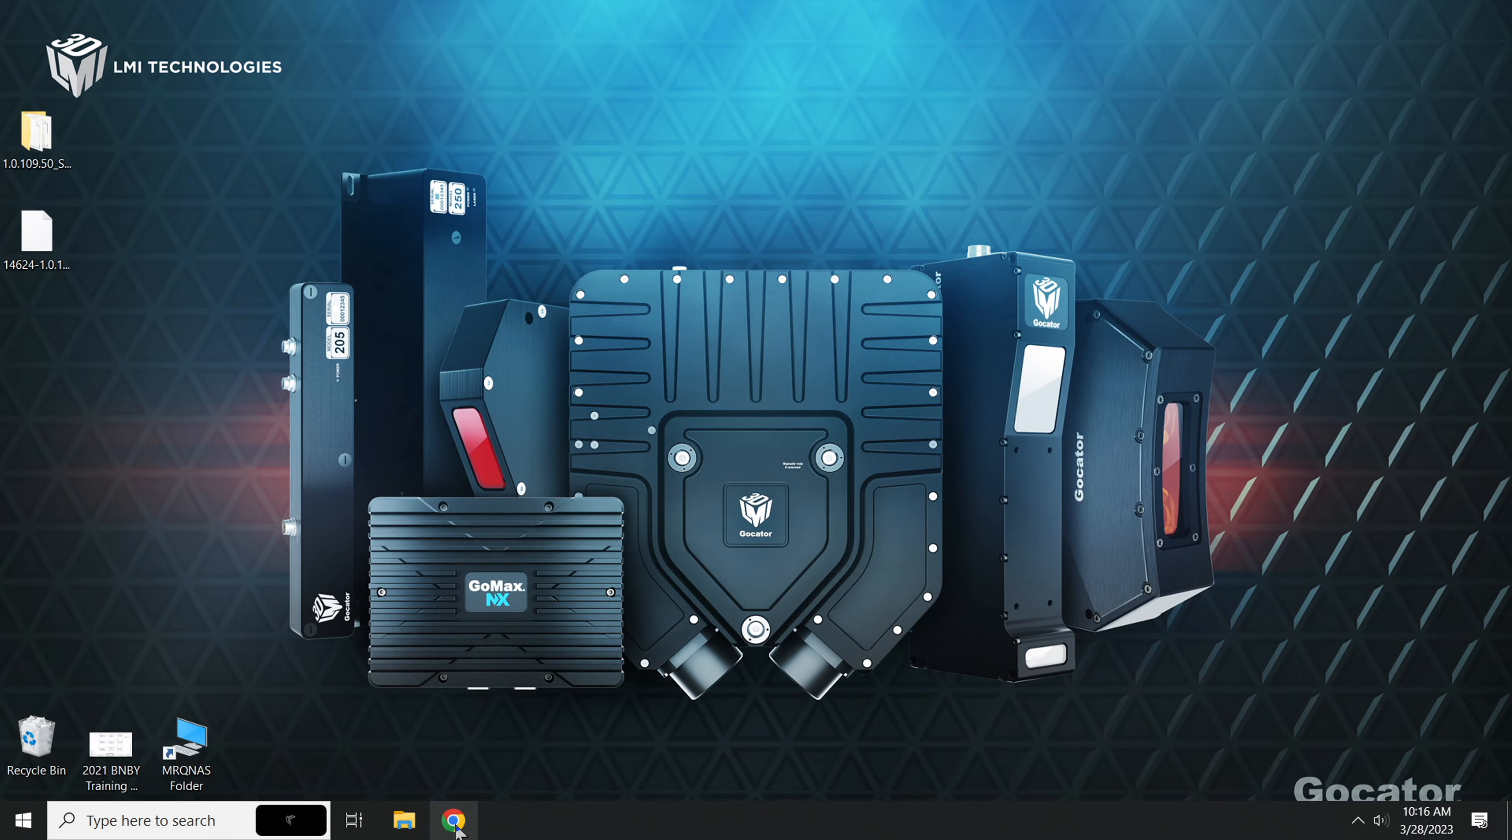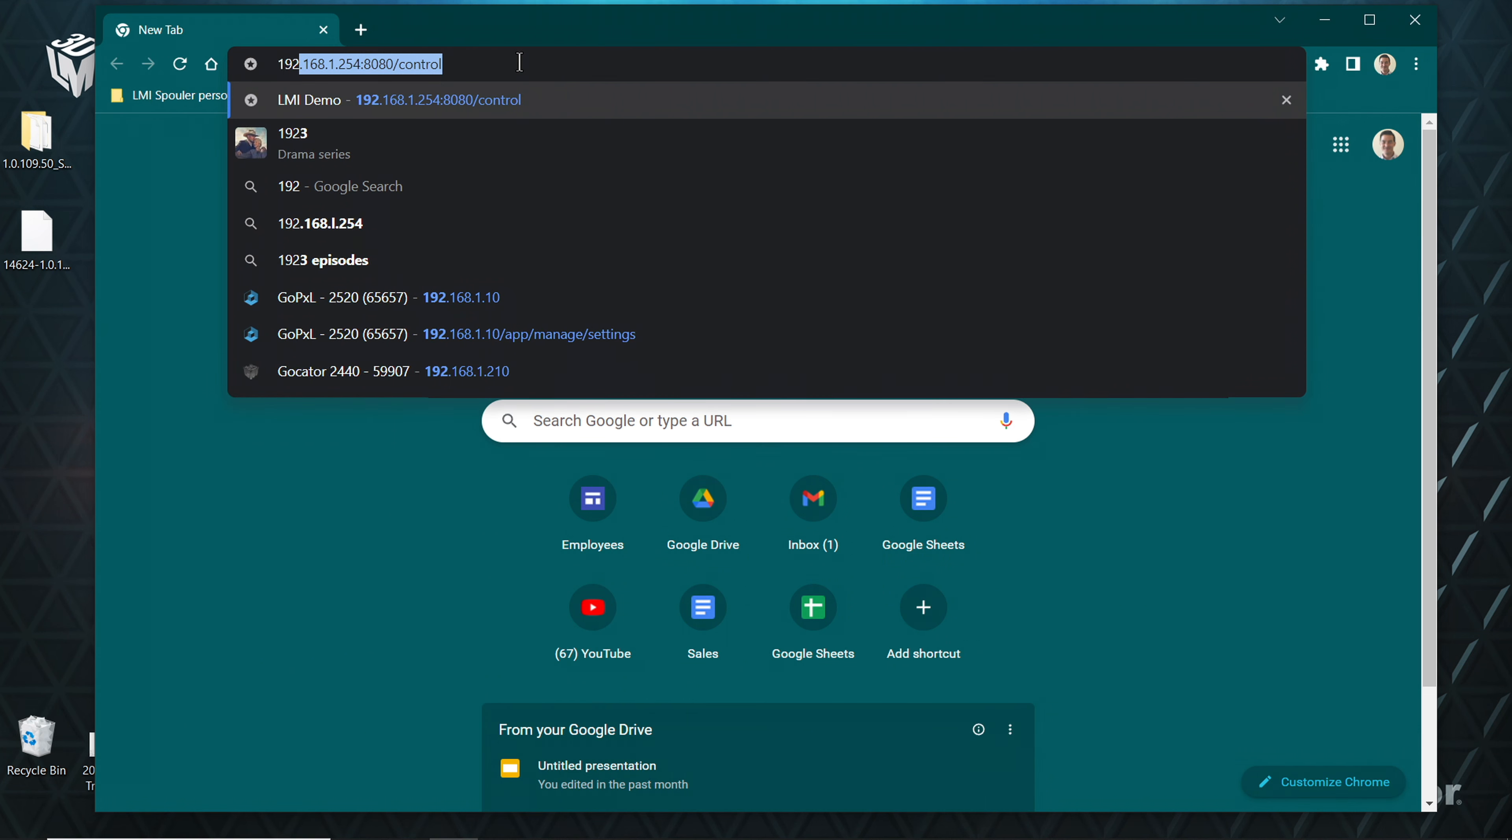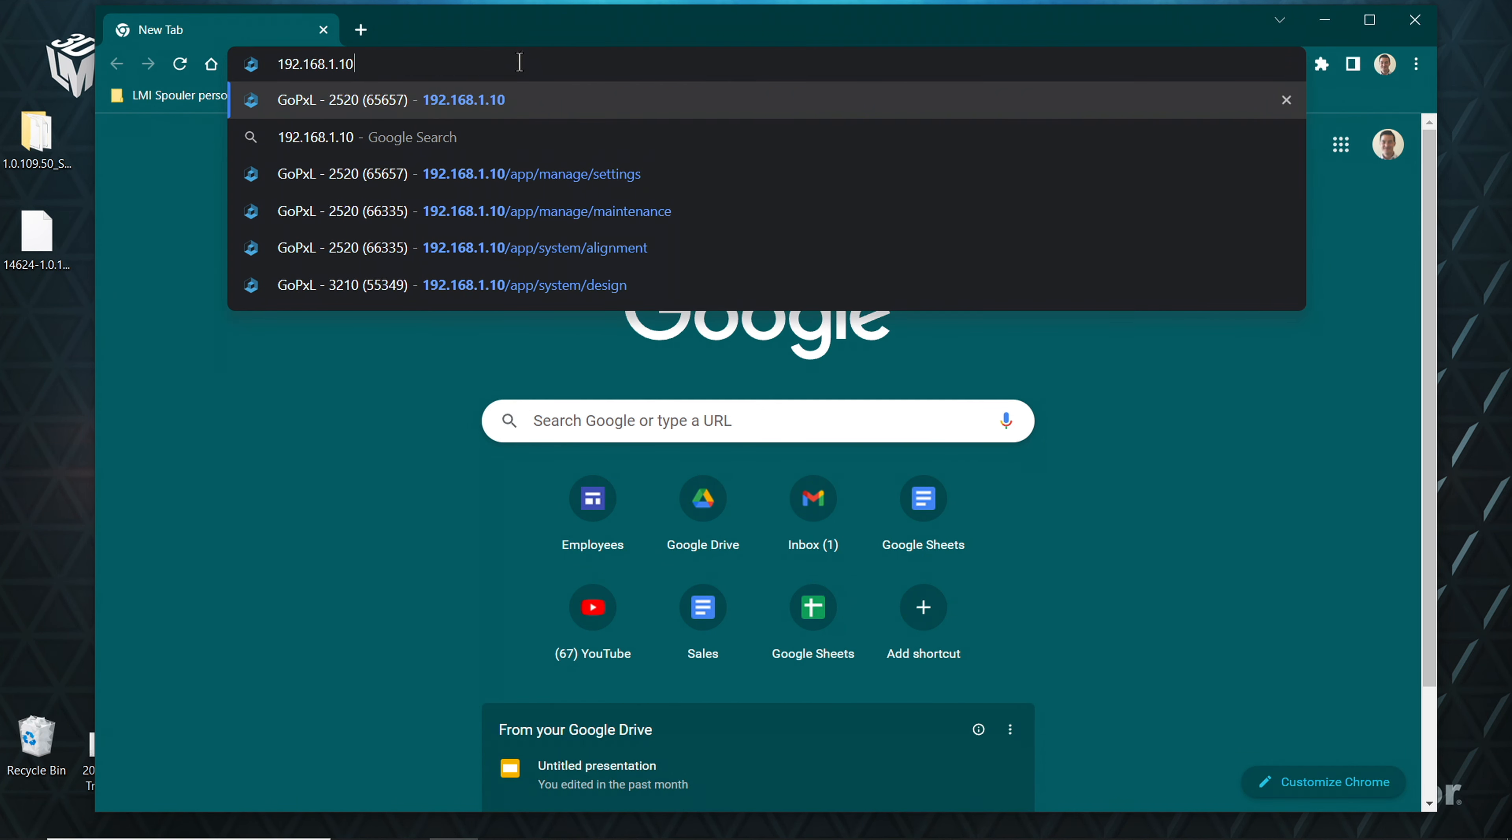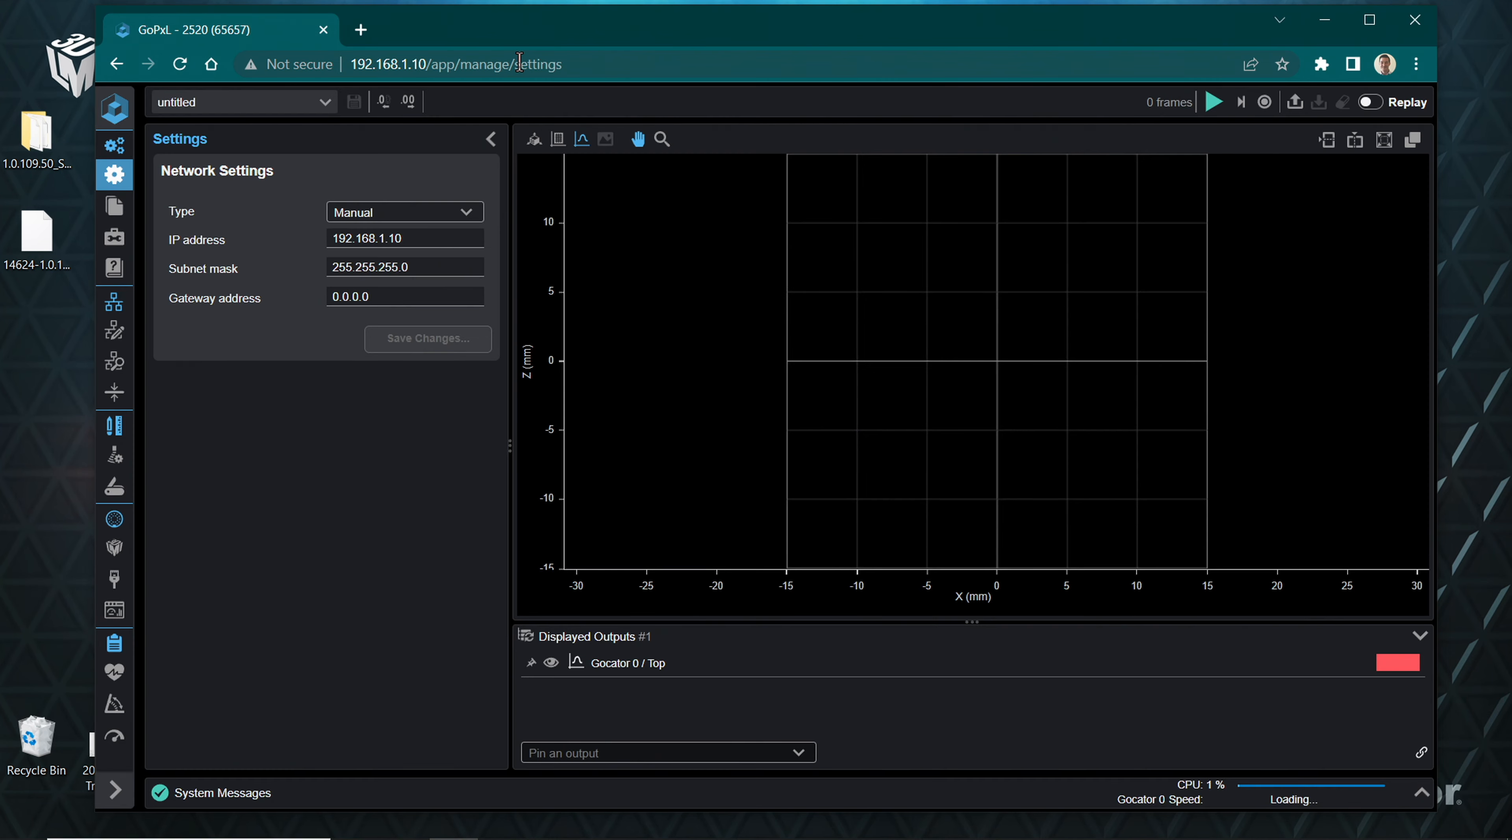Ensure your G2000 series sensor is powered on and the Ethernet cord is connected to your computer. Open a web browser window and enter the sensor IP address. The default sensor IP address is 192.168.1.10. Leave this window or tab open for now.